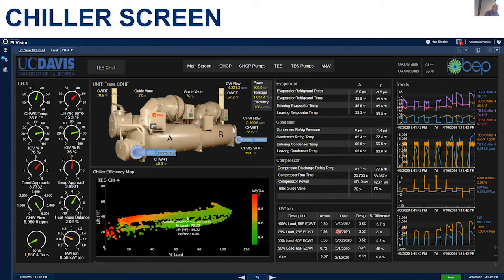We'll do AHRI 550/590 chiller performance tests, which are very expensive. For an electric chiller it could be up to $20,000. For a steam turbine machine it could be higher than that. And you're getting one data point. Why not have your analytics platform run that calculation every 30 seconds? So we're running that heat mass balance from that AHRI 550/590 test instantaneously, and I'm at a 2% heat mass balance, so I know that the instrumentation on my chiller is pretty good. And I have some other approach fault detections here, some rule-based fault detection. Make sure those are dynamic, because approach temperature fault is a function of load. It shouldn't just be the peak value, because the chiller is almost never running at peak, right?